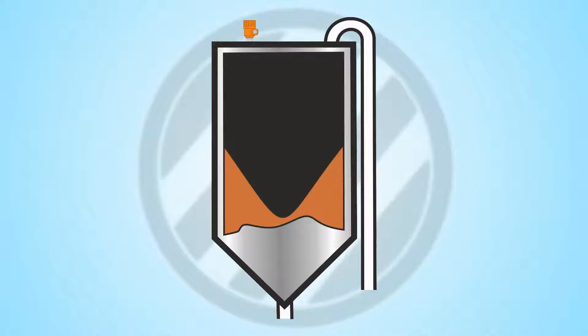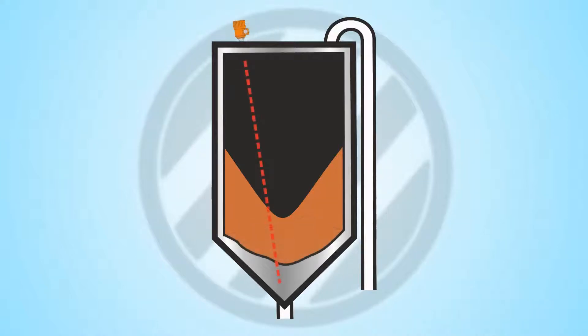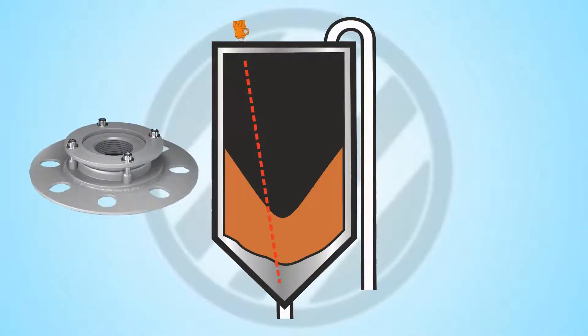In some cases, mounting the radar in a good location may be difficult. For example, you may be forced to put it closer to the edge of the silo, which could cause measurement problems, so a rotational aiming kit is recommended to aim the radar beam to the correct location. This may also help if the vessel has internal structures or if you need to target the bottom of the cone. Please note that for many applications this is not required.